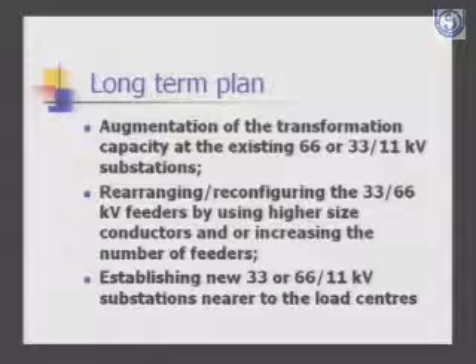The long-term plan generally includes augmentation of transformer capacity at existing 66 or 33 by 11 kV substations, rearranging and reconfiguring the 33 by 66 kV feeders, establishing new substations at load centers, redistributing load between existing and new substations, feeder strengthening, addition of new 11 kV feeders, addition of distribution transformers and LT lines, along with adoption of modern technologies.